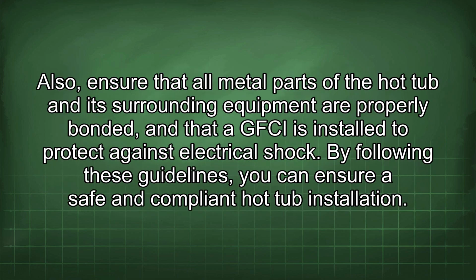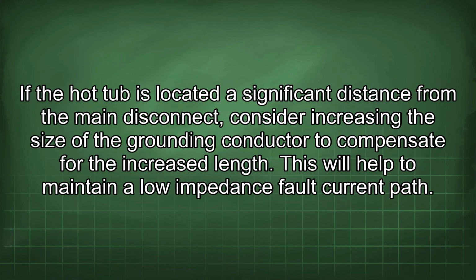Also, ensure that all metal parts of the hot tub and its surrounding equipment are properly bonded and that a GFCI is installed to protect against electrical shock. By following these guidelines, you can ensure a safe and compliant hot tub installation. If the hot tub is located a significant distance from the main disconnect, consider increasing the size of the grounding conductor to compensate for the increased length. This will help to maintain a low impedance fault current path.